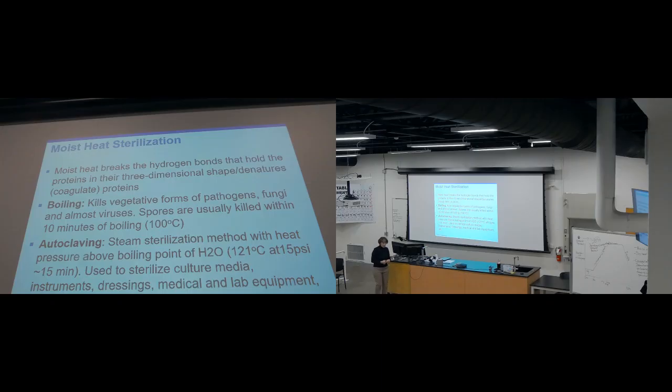When you seal the door of this chamber, the heat of the steam that is produced gets trapped. When you have an exposed instrument or material, like media in this case for the micro lab, this heat penetrates and destroys all forms of life.